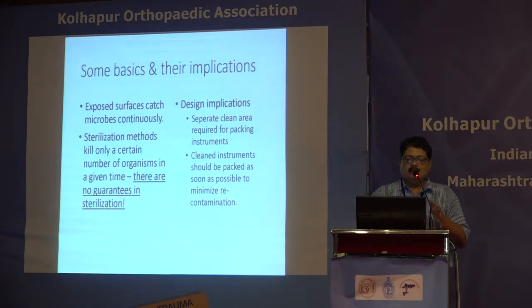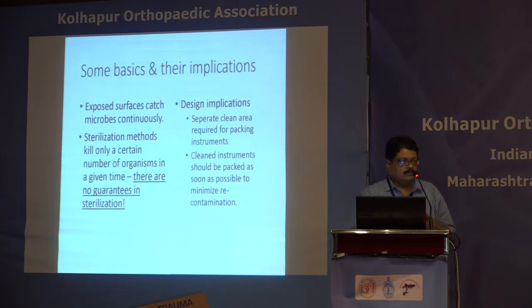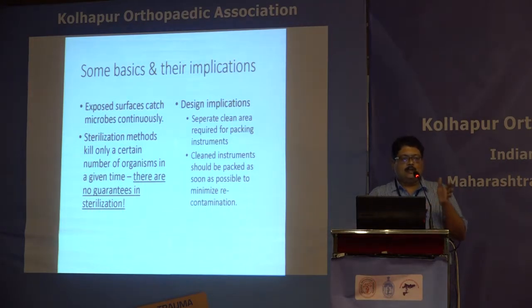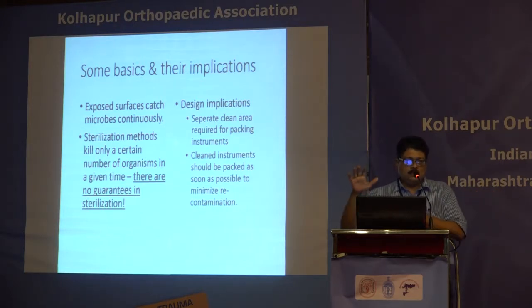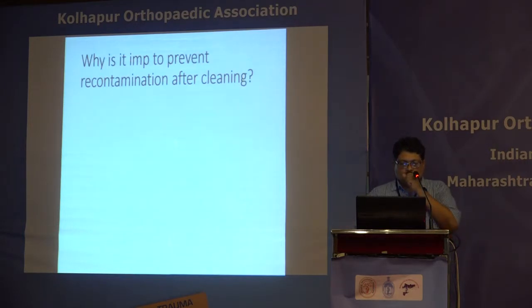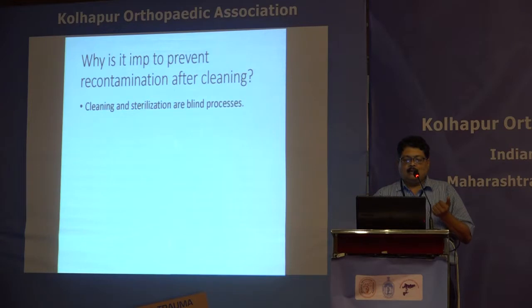Ideally a separate clean area is required for packing instruments. Linen also usually comes to this area, and the cleaned instruments have to be packed immediately as soon as they are ready — they should not be left lying open and then packed two hours later. It has to be one continuous process; only then will it work properly.